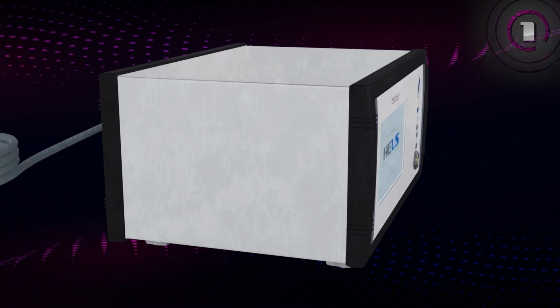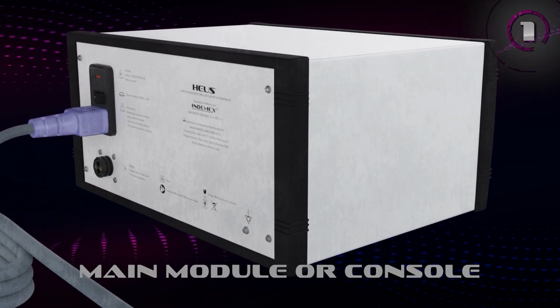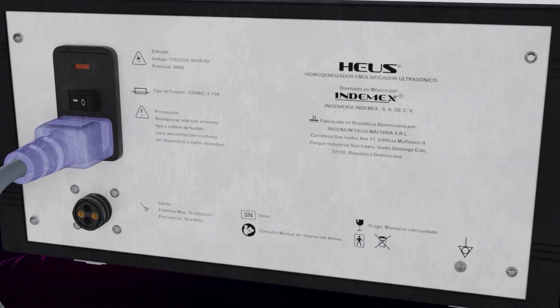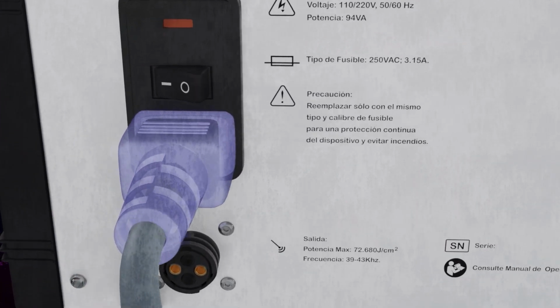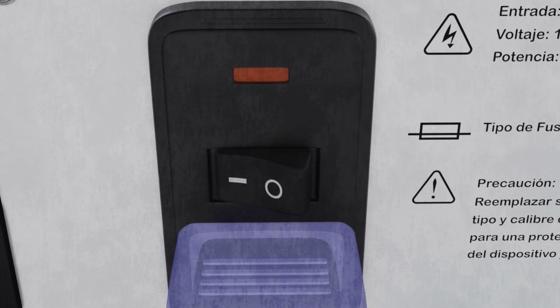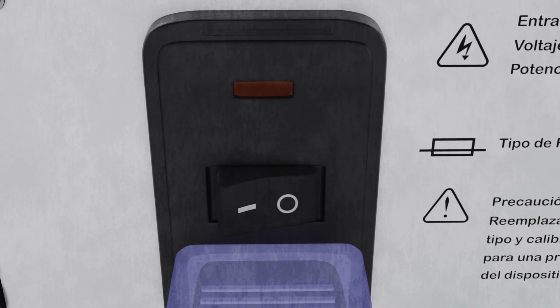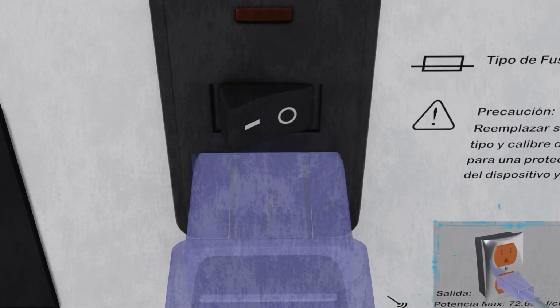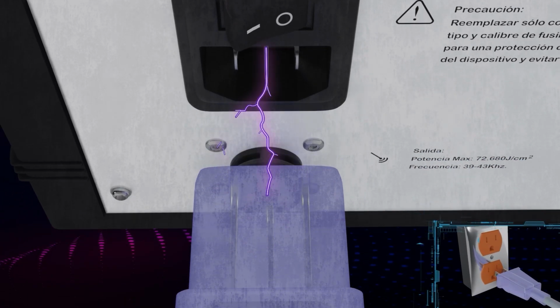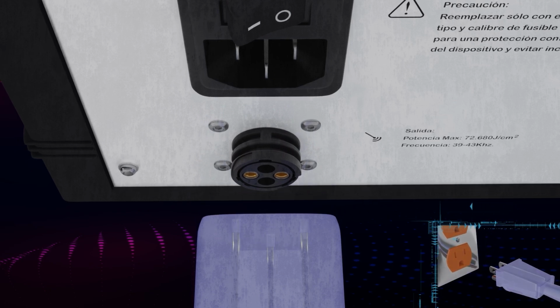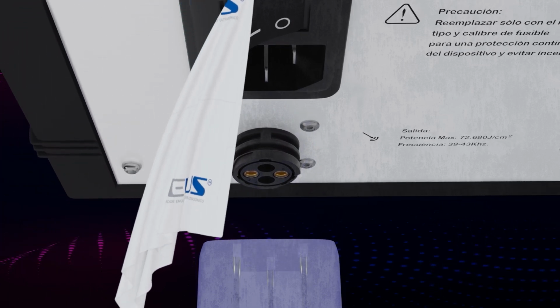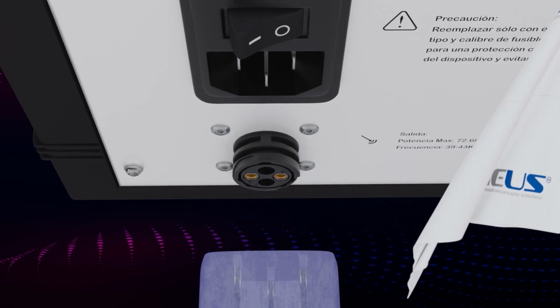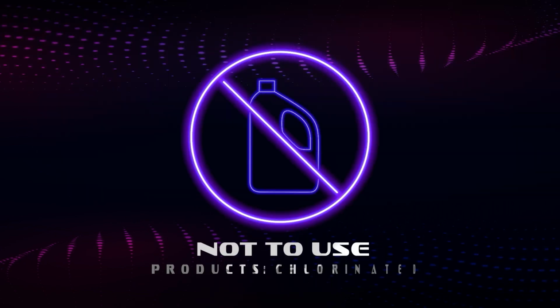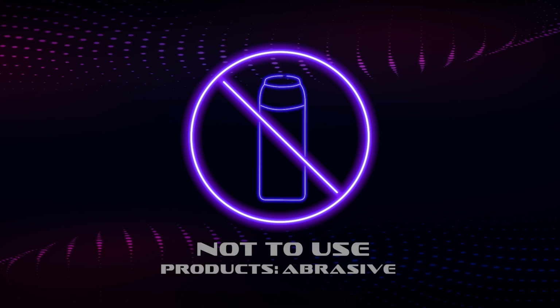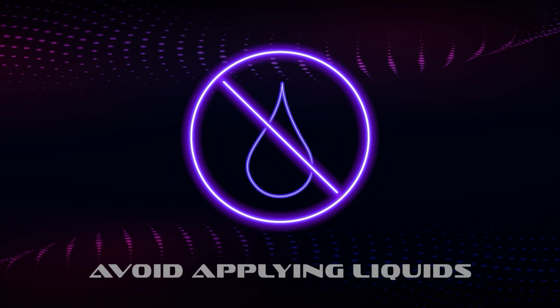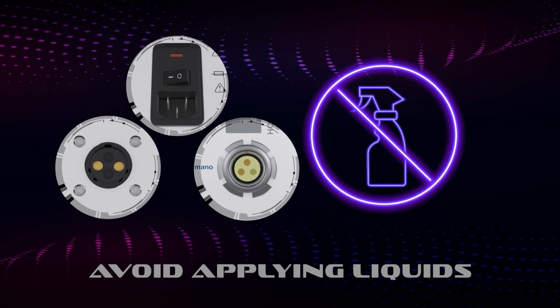1. Cleaning the main module or console after each use is essential to maintain the HELS device in optimal conditions. Follow these steps for effective cleaning. Turn off the device and disconnect it from the main power source to prevent electrical shocks. Use a soft, slightly damp cloth to clean the surfaces on the main module. Remember not to use solvents, chlorinated products, or abrasive cleaning products. Avoid applying liquids or cleaning products directly to the module sockets.